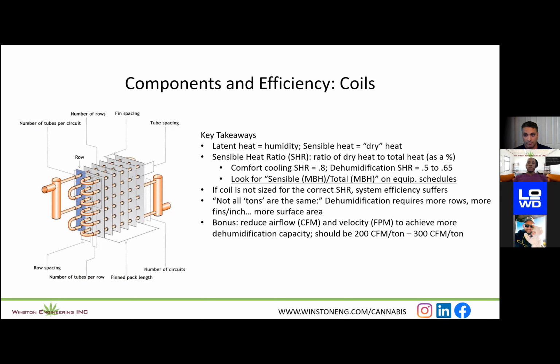That's a significant difference. And where you will find that difference is in the size and depth of the coil, the design of the coil. So when you are looking at coils, if you really want to get into it, look for the number of rows of coil. You generally are going to see probably a 6-row coil in these applications, if not higher. In some cases, you may see a 4-row coil. But ultimately, what you're looking for is more surface area. If you have a high latent application, like a flower room, you need more surface area for that air to pass through so that there is time to wring the moisture out of the air.